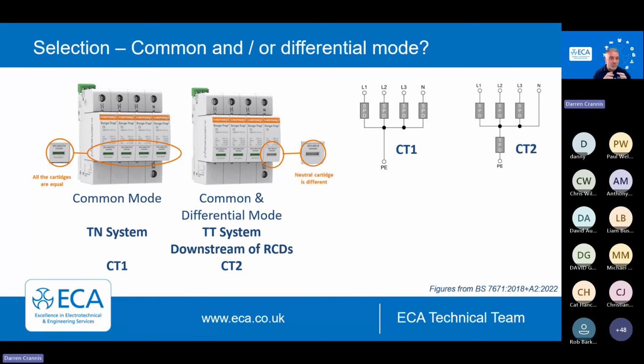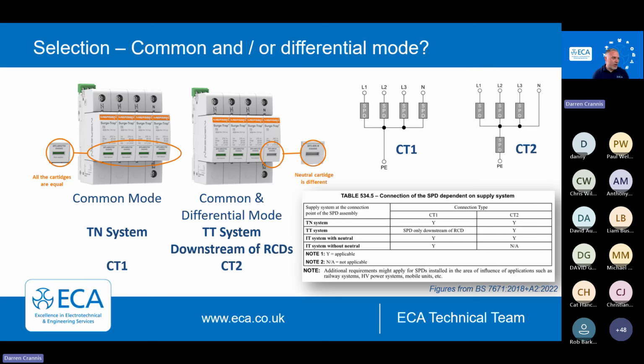On a CT2, which most devices are now by default, they will use a spark gap or a gas discharge tube between the neutral and PE. And that little gap there means that RCDs aren't going to trip. So to highlight the regulations of this again, your CT1s are for TN systems, CT2s can be used everywhere.